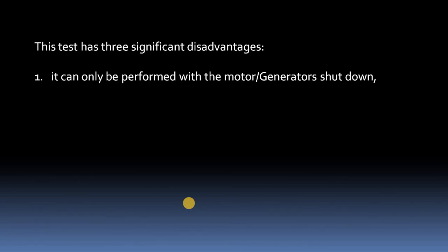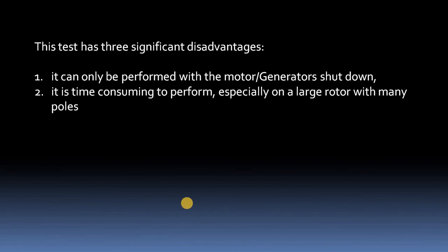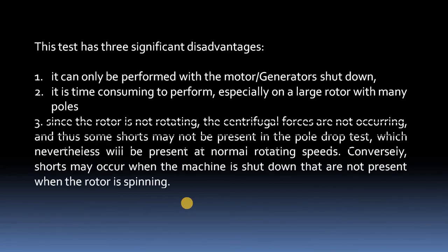One disadvantage is it can only be performed when the motor or generator is in idle condition — at rest. It is also time-consuming to perform, especially on large rotors with many poles. Furthermore, since the rotor is not rotating, centrifugal forces are not accounted for. Some shorted turns in the field poles only exist when there is rotation due to centrifugal forces, and those cannot be identified by the pole drop test.